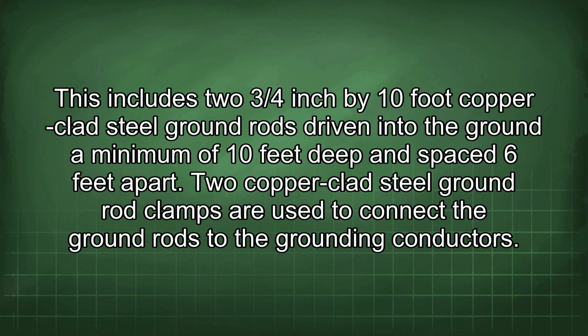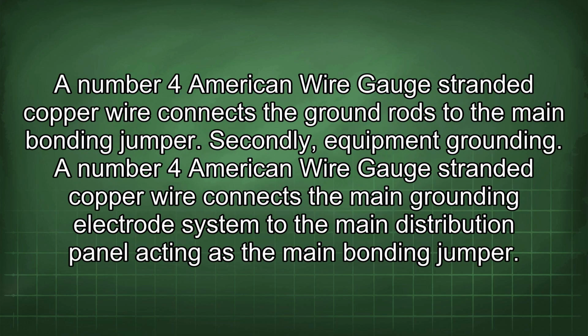Two copper-clad steel ground rod clamps are used to connect the ground rods to the grounding conductors. A number 4 American wire gauge stranded copper wire connects the ground rods to the main bonding jumper. Secondly, equipment grounding. A number 4 American wire gauge stranded copper wire connects the main grounding electrode system to the main distribution panel, acting as the main bonding jumper.